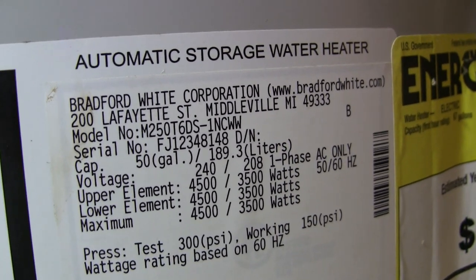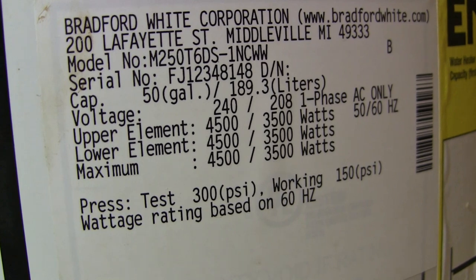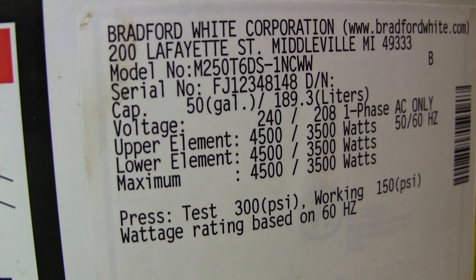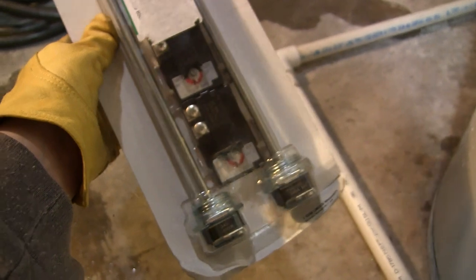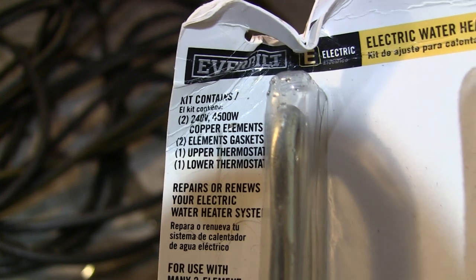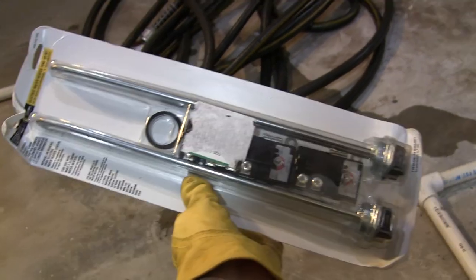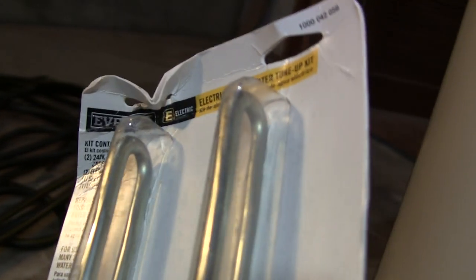There's the model number — it's a 50-gallon tank. It gives you the voltages; it's on 240V, 4500 watts for the upper and lower elements. I've already ordered the whole kit — I've got the elements and I'm going to replace the thermostats, the whole shebang in one shot. The kit was like 20 or 25 dollars on eBay or Amazon. It's an Everbilt kit — these are pretty universal. I'll show you everything I'm doing.